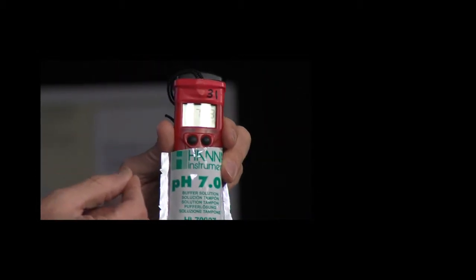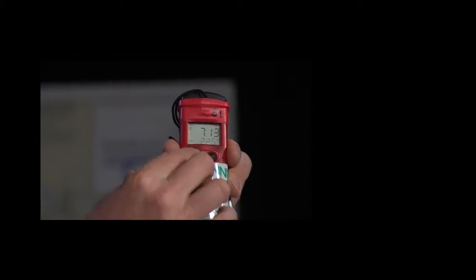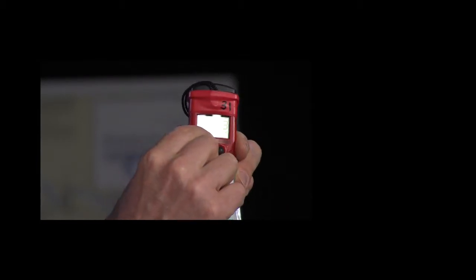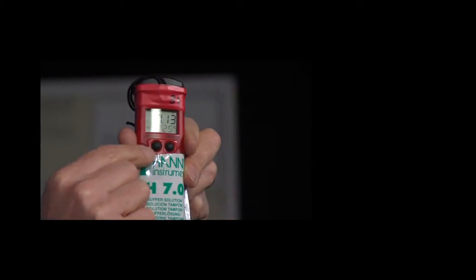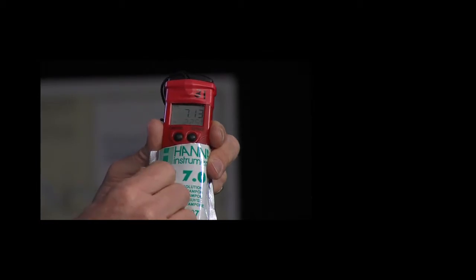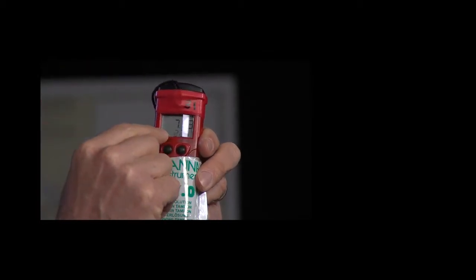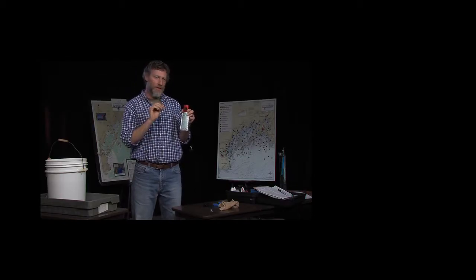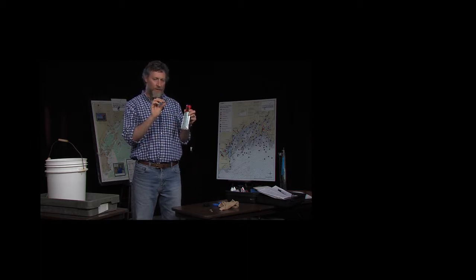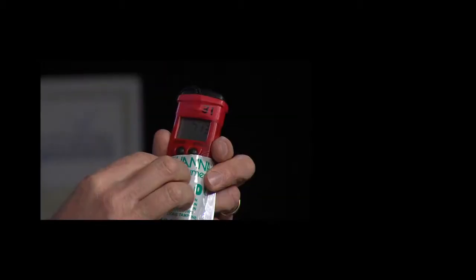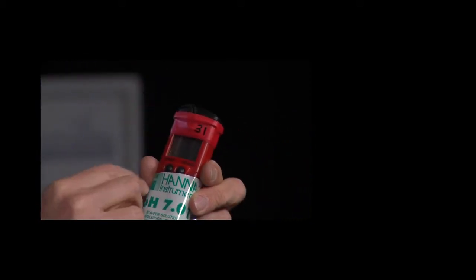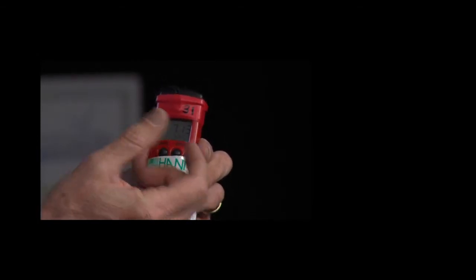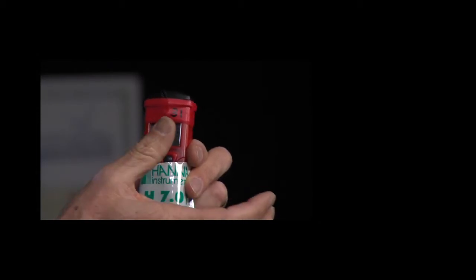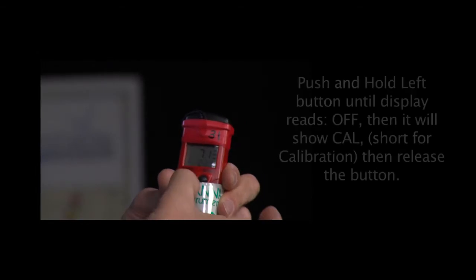So the steps to calibrating it are, we're going to push the left button in once and hold it, and on the display it will say off, and then in a second it will show cal, the letters C-A-L at the bottom. Once you see the letters C-A-L, you take your finger off the left button, and it will start its calibration, which takes a few minutes. The numbers sort of flash a little bit, and then it will go from 7.0, and it will want you to switch to a different solution. I mentioned before that you can calibrate with a 7, a 10, and a 4. So it will then display a 4. When it displays the 4, you push the button again, and it will say OK, which means it's accepted the 7 calibration.